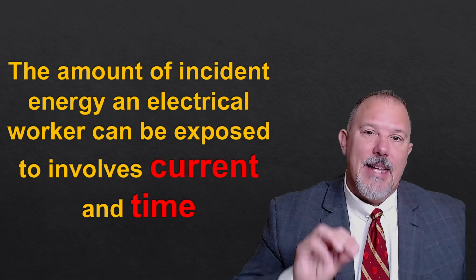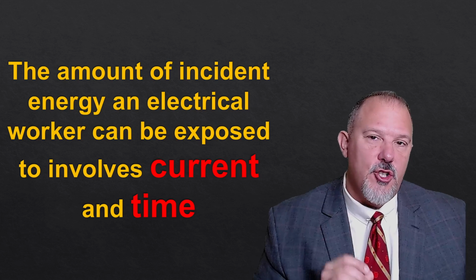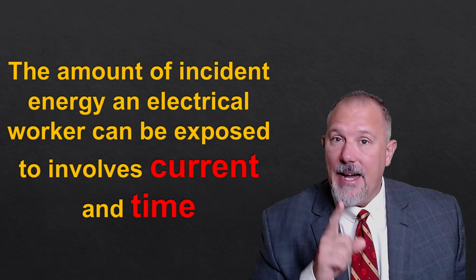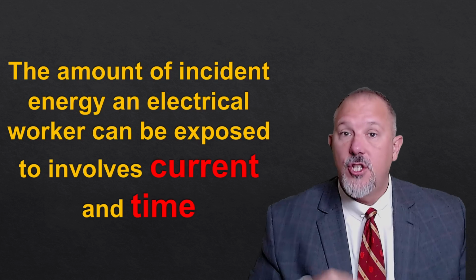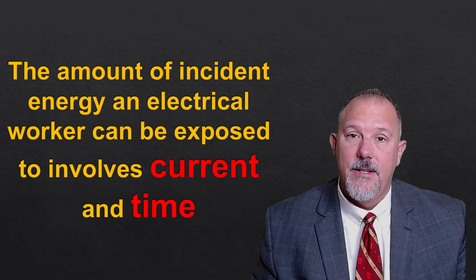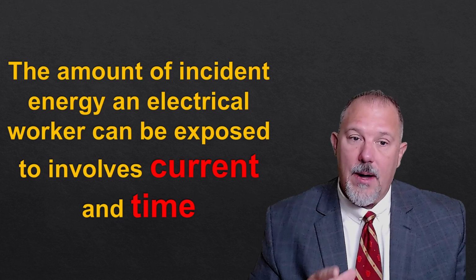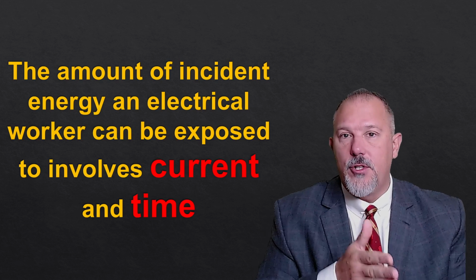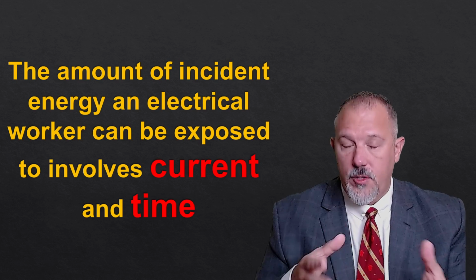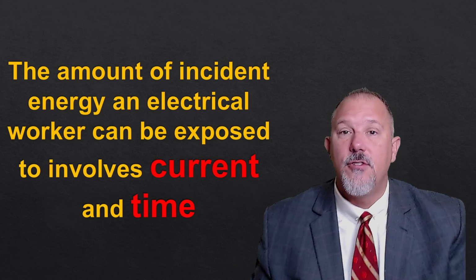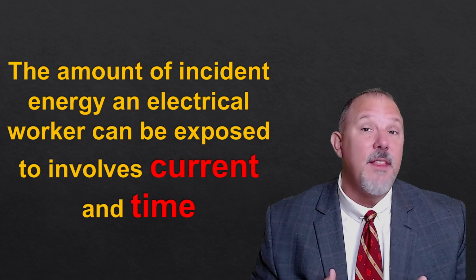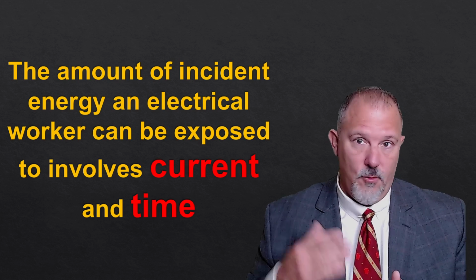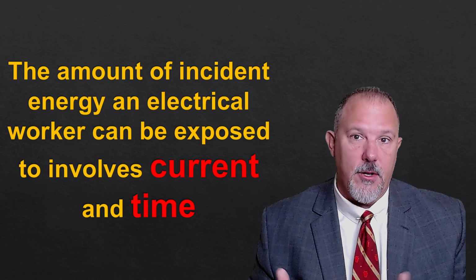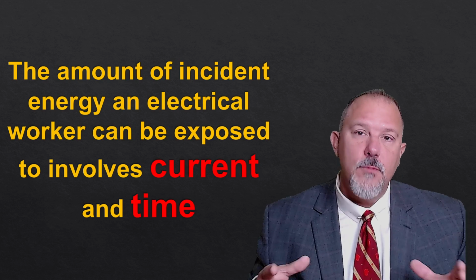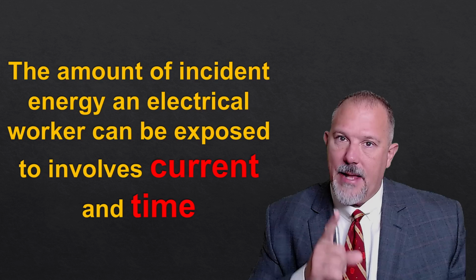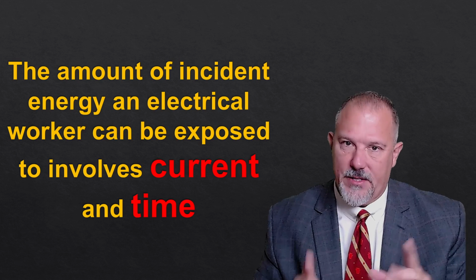So current and time. I may not be able to control the current as easily as I can control the time, to reduce severity, not likelihood. Remember, when I'm talking about reducing time, which means I'm reducing the amount of energy I let go, that means the event has occurred. I haven't reduced the likelihood of that event occurring because it occurred. I'm reducing the severity. And that's important, remember, there's two pieces of risk, all right?